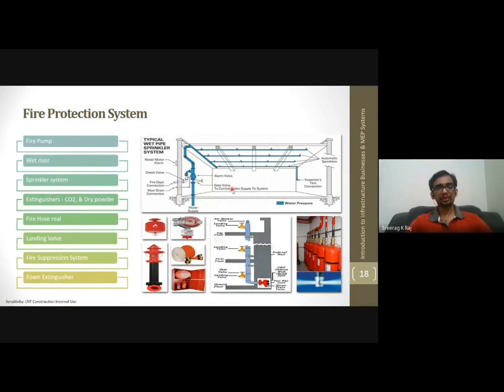And the sprinkler system, you know, if there is any fire, if the temperature reaches beyond a particular level, then there is a bulb in that particular portion, and that bulb will burst and start spraying water in that particular area. So automatically it will give the sense to the nearest zone control valve. A zone control valve is nothing but, the entire building will be divided into different zones, and that valve will detect the signal and give the signal back to the fire alarm panel.